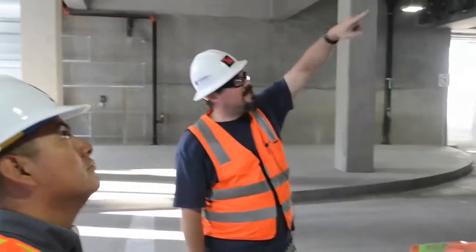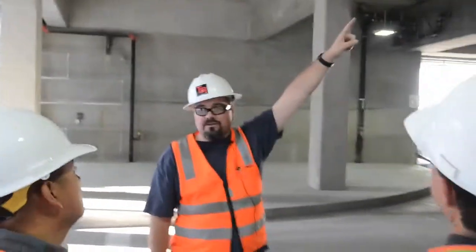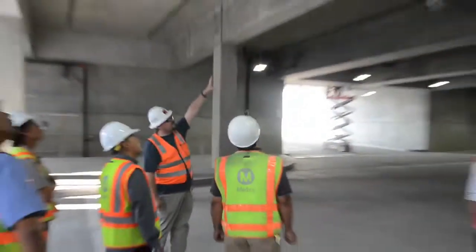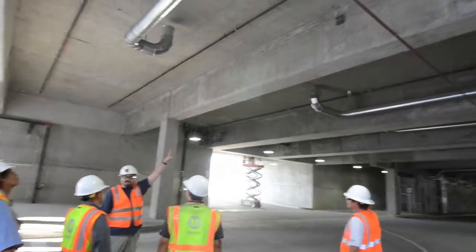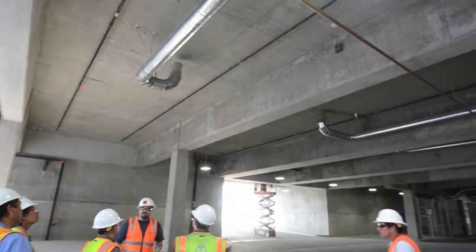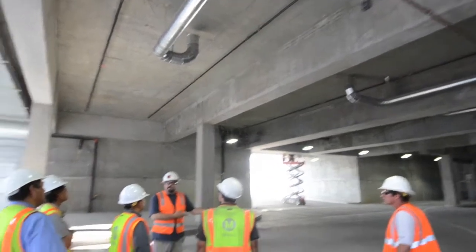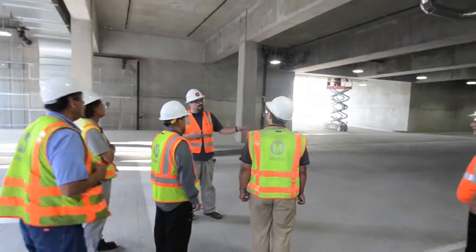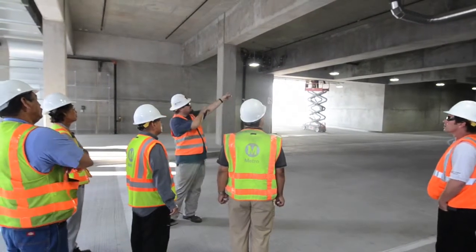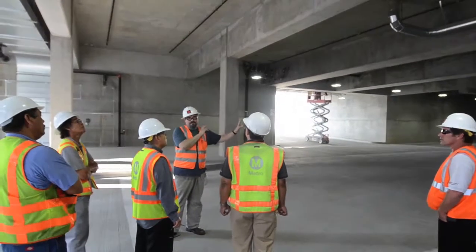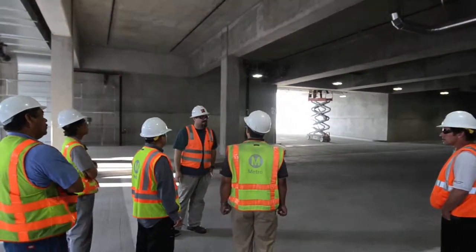That's correct. And also when that thing goes off, like he was saying, that gray box has a piezo that makes a noise. And you'll also see that relay's little blinky light in the middle. It's really hard to see because it's green, but it will go solid red. So that's another indication of which one is going off. But like he said, if it builds up too much, it'll probably be flushed out before you even get down here to see which one, because it automatically resets once the big fans out back kick in. That's what all this ducting is for, to take care of all the gases. It'll suck it out and blow it all out within probably about 5 minutes or so.